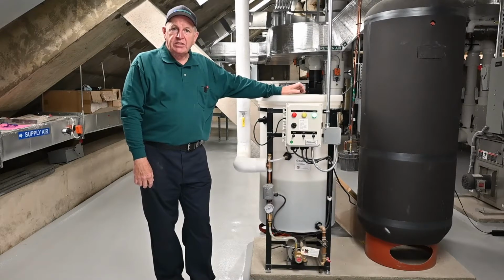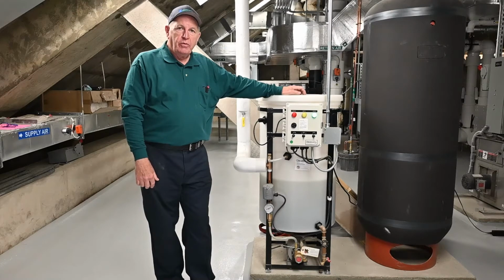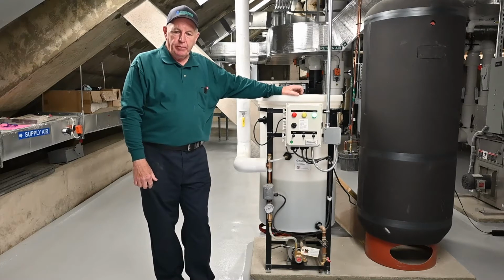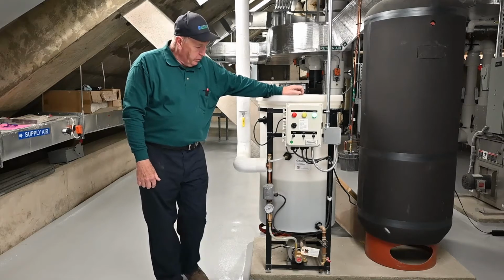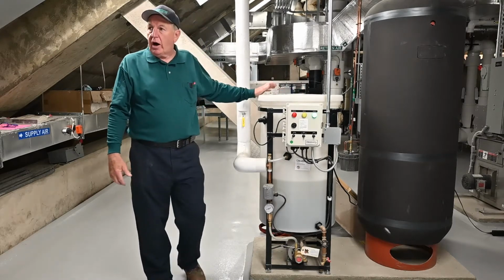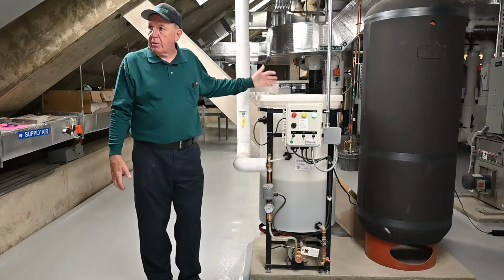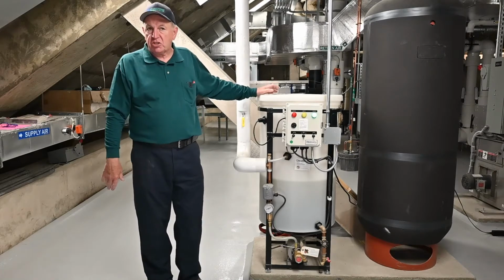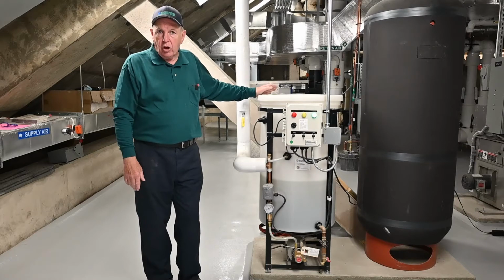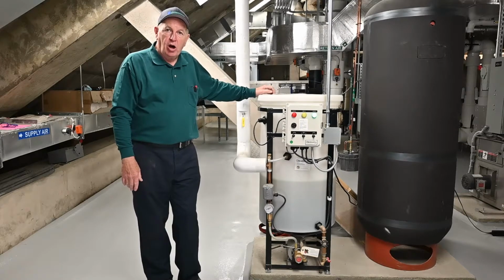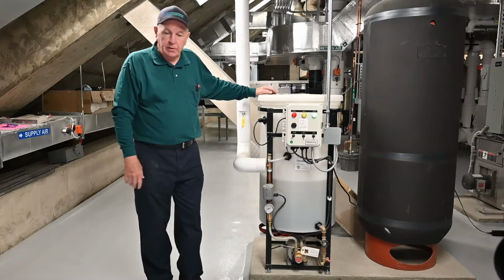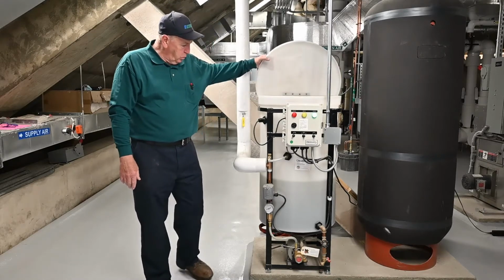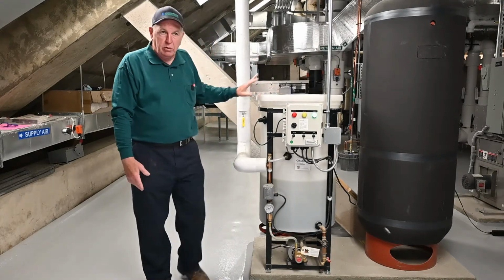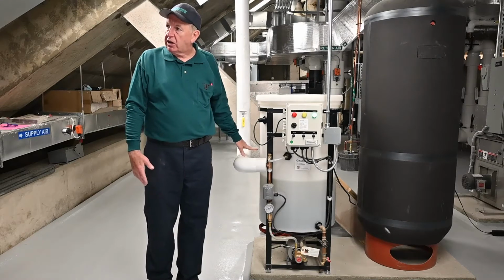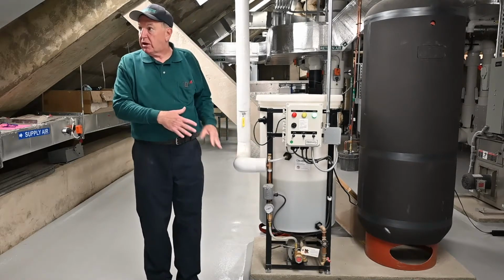Okay, we're here at Rare Books. This is the glycol makeup feeder for the chilled water system for the chiller and air handler. You can't just add city water to a system that has glycol in it because it would dilute the mixture. So we're trying to maintain a 30% glycol mix. It's a propylene glycol, so it's non-toxic. You can add some here, but you can add a 30% mix so that when it pumps into the system, it's already at the right level.